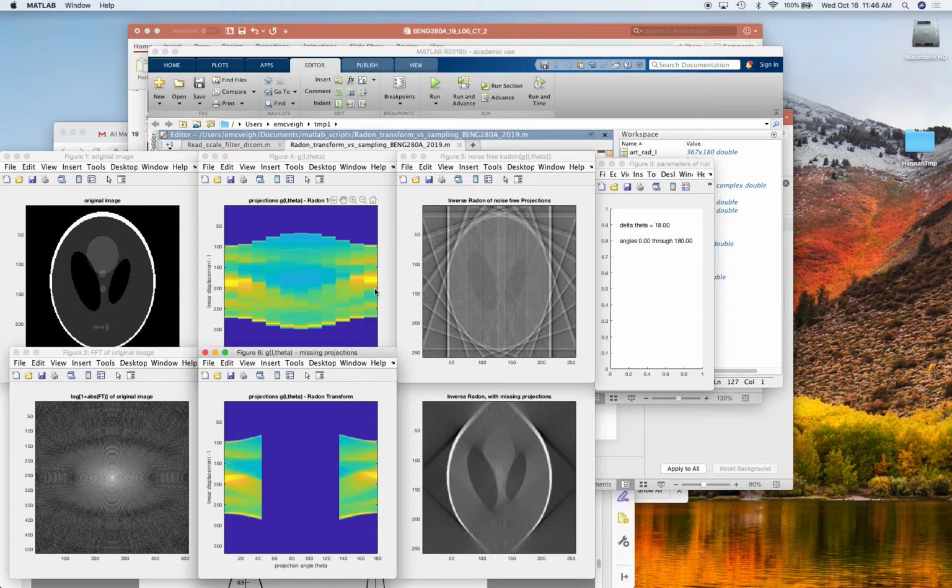With other imaging techniques, like say if you're doing back projection MR, which you can do, instead of Cartesian MR, you can do polar MR, and it's very similar to this. There, it's just a matter of time. So I can get an image in half the time. If one image takes 100 milliseconds and one image takes 50, and something's moving, it's better to get it done in 50. And so you get high time resolution, but lower spatial resolution. So you're trading off time resolution and spatial resolution. So these things are always in a balance, right?